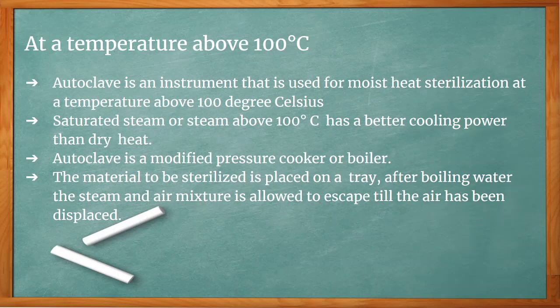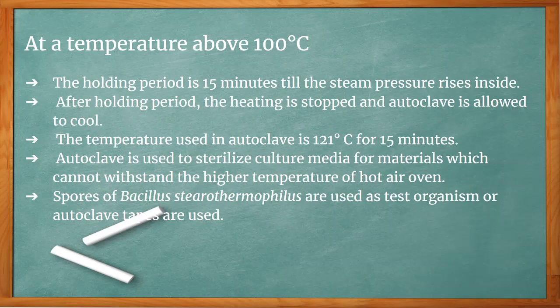At temperatures above 100 degrees Celsius, an autoclave is used for moist heat sterilization. Saturated steam above 100 degrees Celsius has better killing power than dry heat. The autoclave is a modified pressure cooker or boiler. Material is placed on a tray, water is boiled, and the steam-air mixture is allowed to escape until air is displaced. The holding period is 15 minutes at 121 degrees Celsius. After the holding period, heating is stopped and the autoclave cools. It is used for culture media and materials that cannot withstand the higher temperatures of the hot air oven. Spores of Bacillus stearothermophilus or autoclave tapes are used as test organisms.